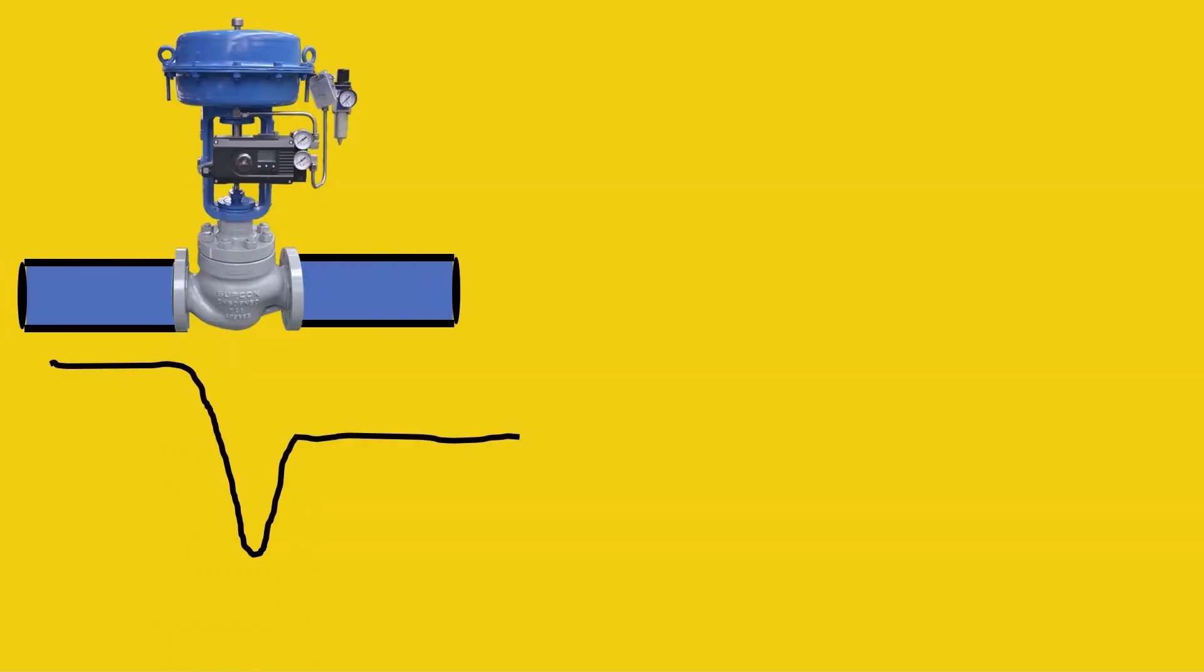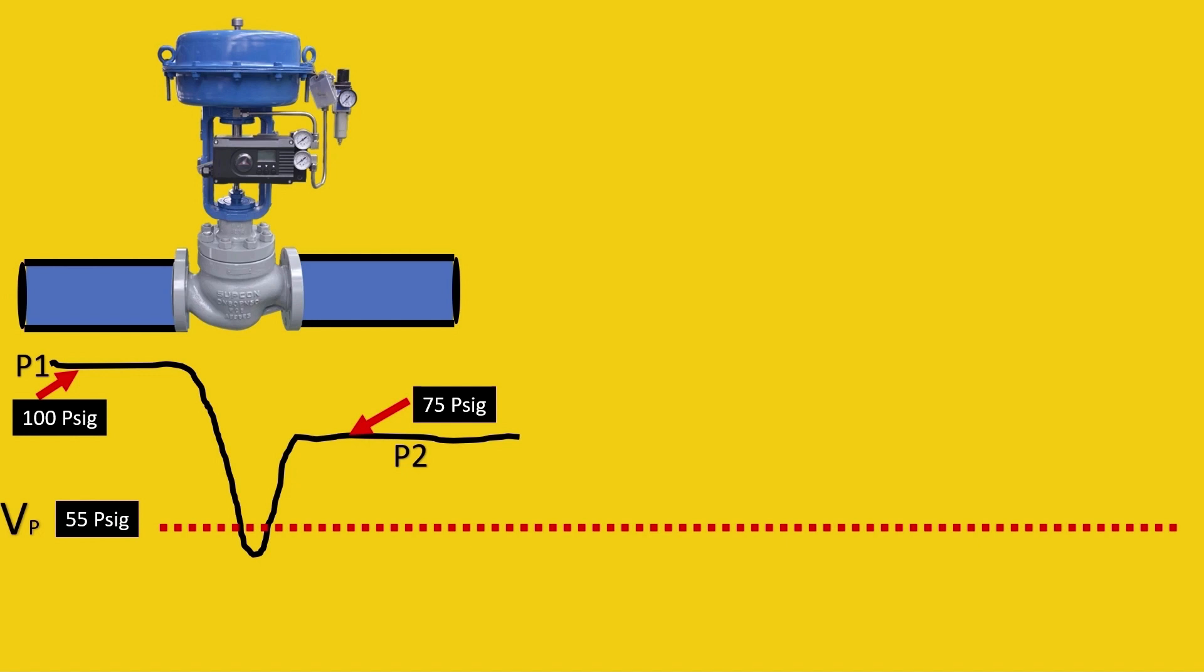Here is our valve and here is our pressure drop that happens across the valve. Let the pressure before the valve P1 be 100 psi and the pressure P2 after the pressure drop let it be 75 psi. What happens here is let the vapor pressure be 55 psig. So the curve is going below the vapor pressure, so cavitation will happen.